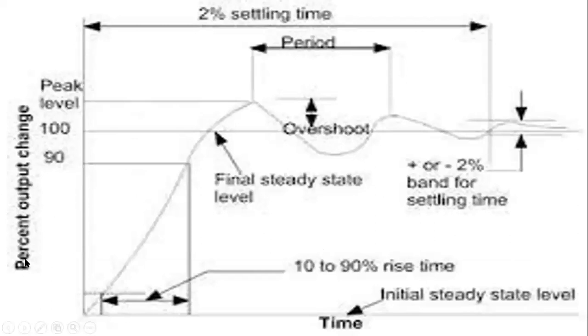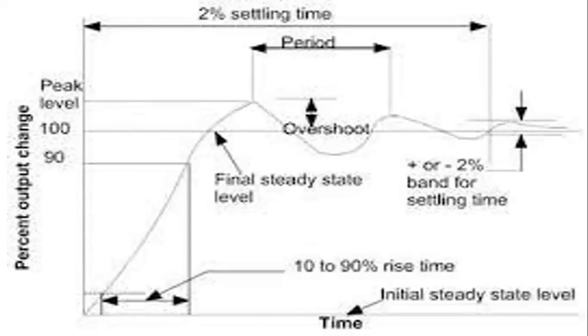Let's understand this with a diagram. The y-axis shows percentage output change and the x-axis shows time. If you give a step input of 100 degrees centigrade — meaning 100% output change — you expect the output to settle there. A step input is like inserting a thermometer instantaneously into a bucket of hot water already at 100°C.